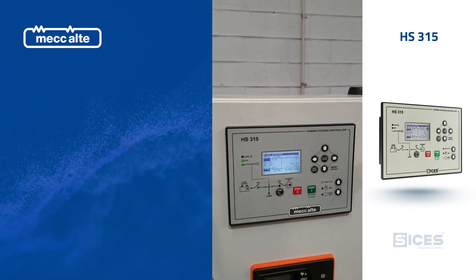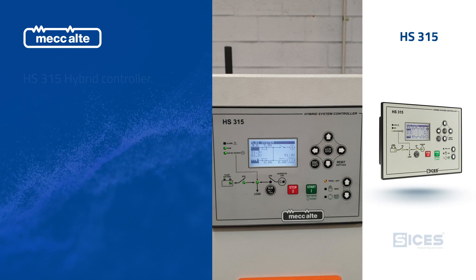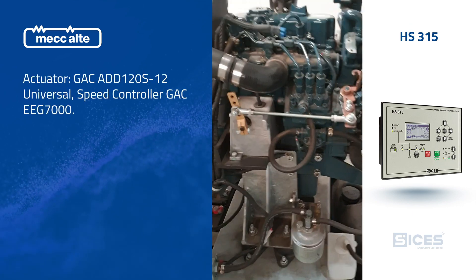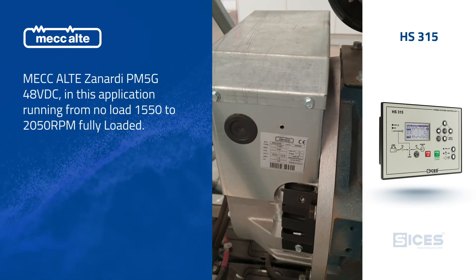Here we have a SICES HS315 hybrid controller. We're just going to give you a little demonstration on how this unit works. Here we have the Kubota engine, GAC actuator, and a Zanardi PM5G alternator running at 1500 RPM.